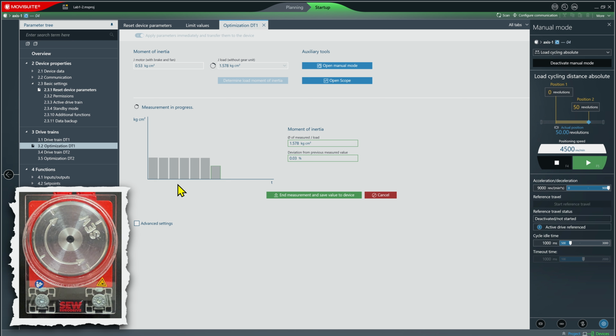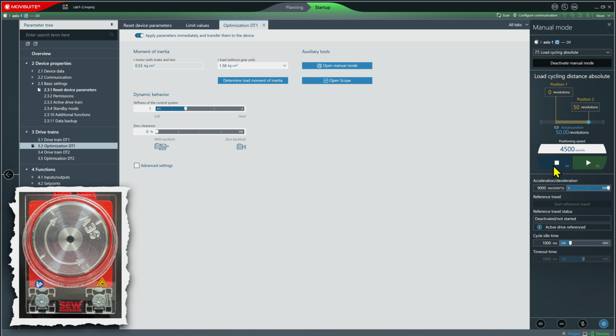And all I have to do is wait until the bars stabilize, they're about the same height, and this button turns green, which it already has done. So I've got my inertia value. I'm going to just click End Measurement, Save Value, and I'm going to stop my drive from cycling. And there's my inertia value right there. That's what my flywheel is. I'm going to set my stiffness right here to 1. In fact, it's already set to 1. That's a good starting value. My drive is basically tuned.